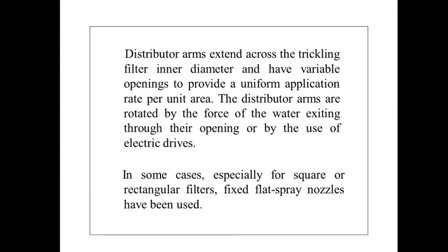Okay, so the distributor arm extends across the trickling filter inner diameter and has variable openings to provide a uniform application rate per unit area. The distributor arms are rotated by the force of the water exiting through their openings or by the use of electric drives. In some cases, especially for square or rectangular filters, fixed flat spray nozzles have been used.